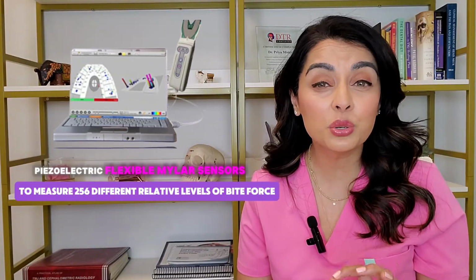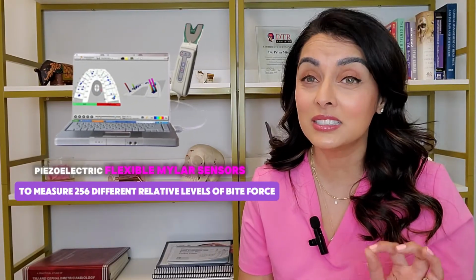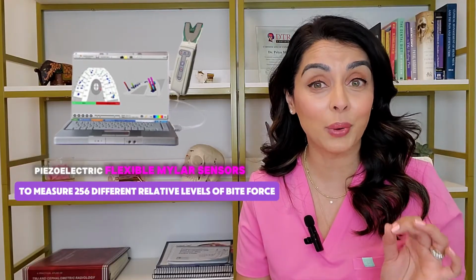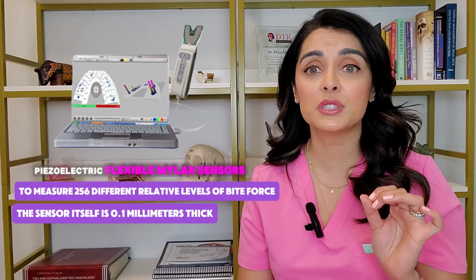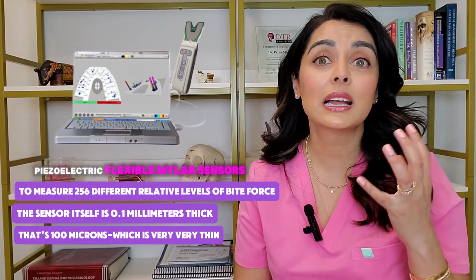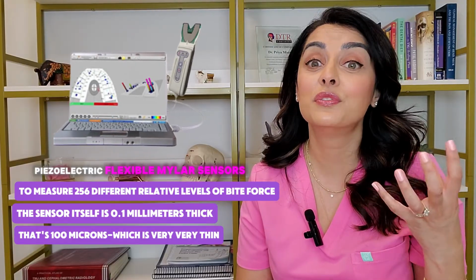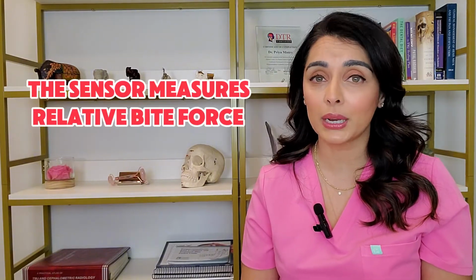The TScan 10 is a biometric technology that uses very precise piezoelectric flexible mylar sensors to measure 256 different relative levels of bite force. The sensor itself is 0.1 millimeters thick. That's 100 microns, which is very, very thin. For perspective, there's 1,000 microns in a little bitty millimeter. So the sensor is very thin. And again, the sensor measures relative bite force.